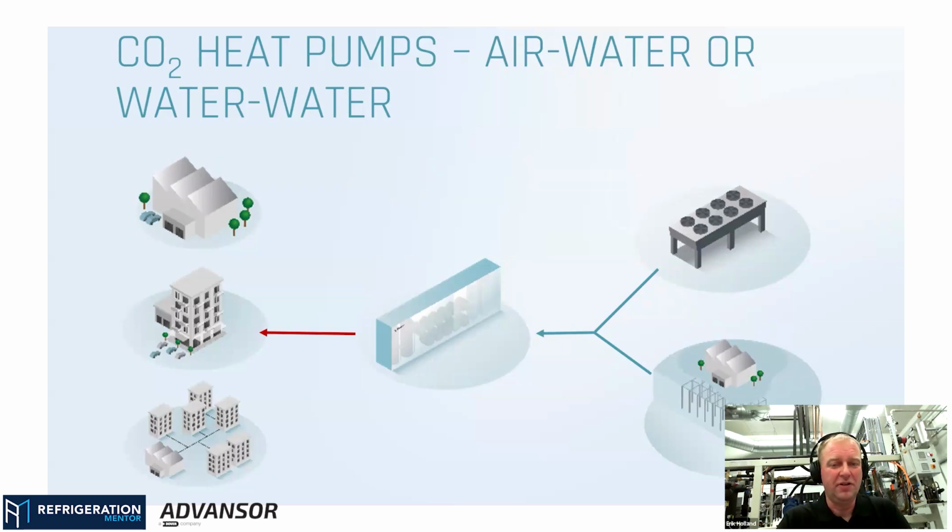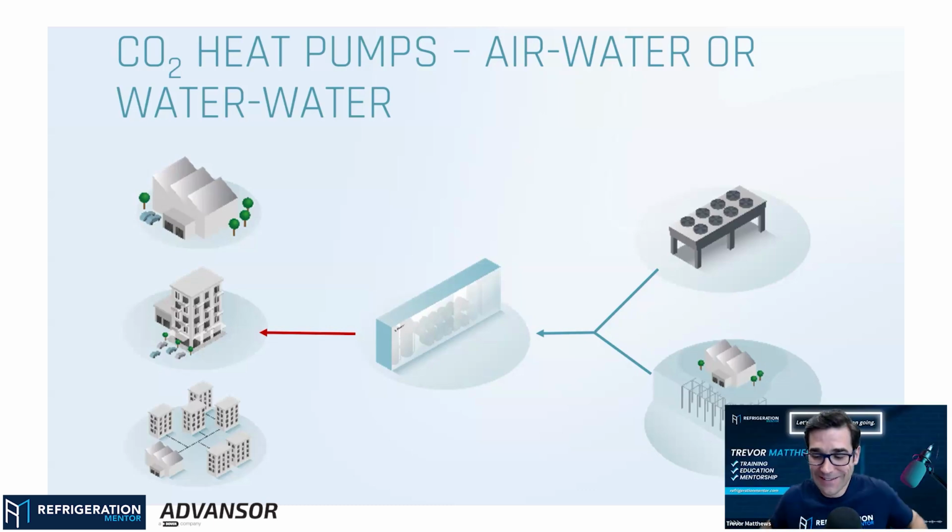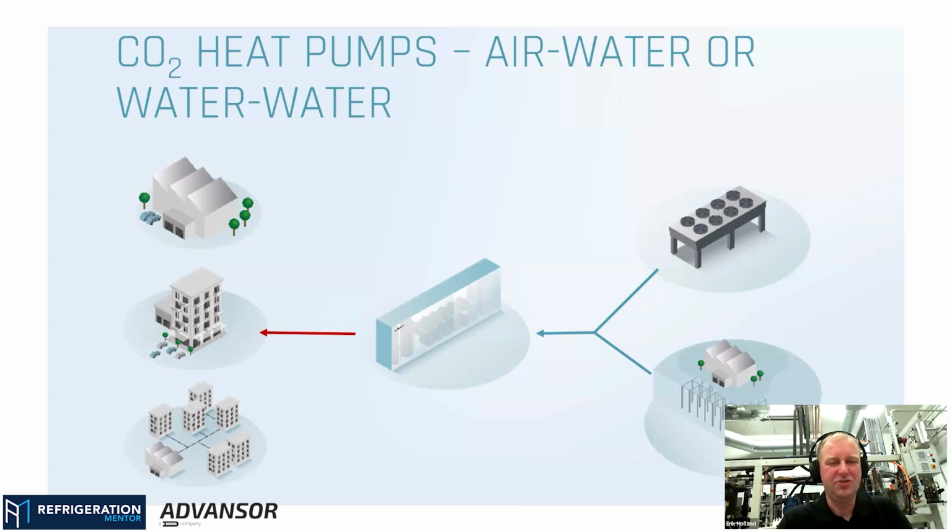And unfortunately, the gas cooler is probably not really an exciting component. It's mostly just a box of fans, right? So it's super boring. It's always on the roof in the rain, so nobody likes that one. But it's super important that all these things work before we can start the unit. Because if we have a faulty gas cooler and we try to start the rack, all kinds of weird things can happen. You could go into a gas loop.